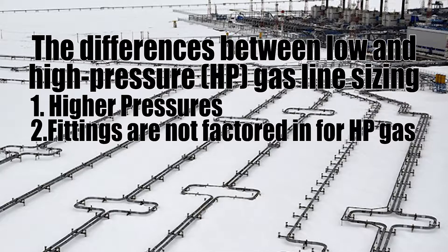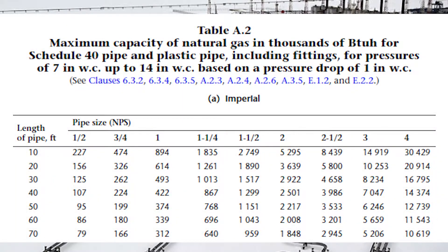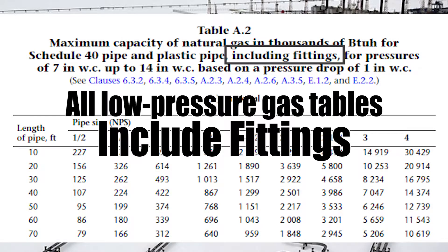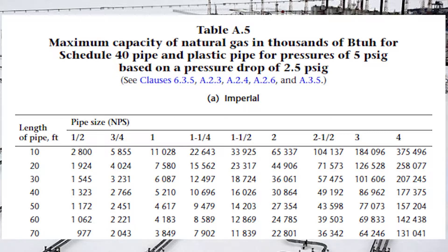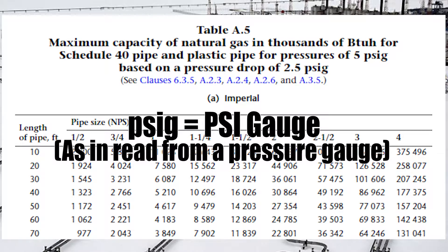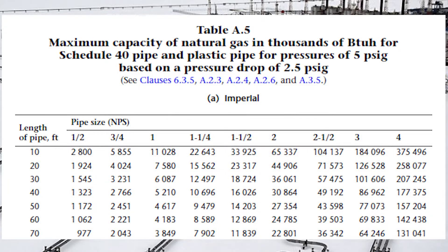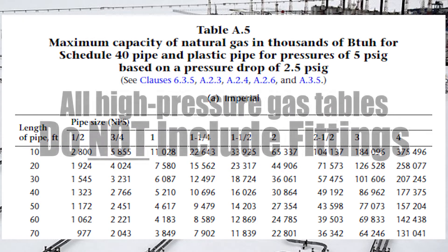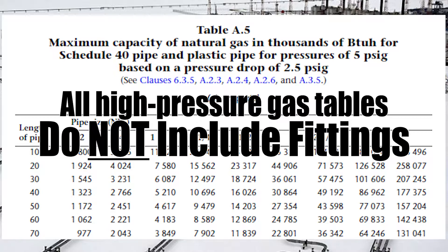The next difference comes into how we factor in fittings in the gas line for high pressure compared to low pressure. Low pressure Table A2 states maximum capacity of natural gas in thousands of BTUs for SCH 40 pipe and plastic pipe, including fittings — so all the low pressure gas tables include fittings. But Table A5, the first high pressure gas line sizing table, covers SCH 40 pipe and plastic pipe for pressures of 5 psi based on a pressure drop of 2.5 psi, and notice it doesn't mention including fittings. High pressure gas line sizing tables do not include fittings, so we have to do an extra step to factor in for them.